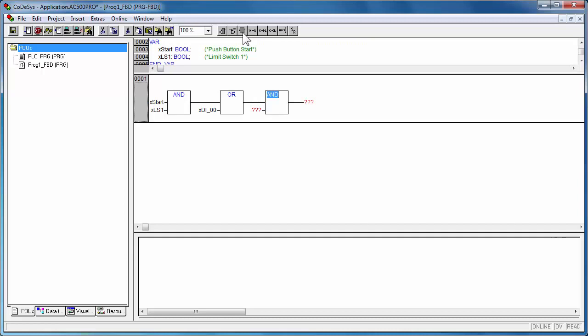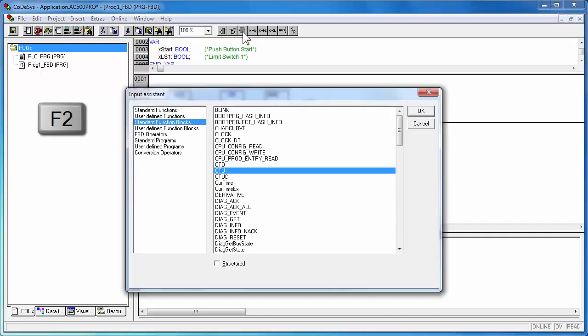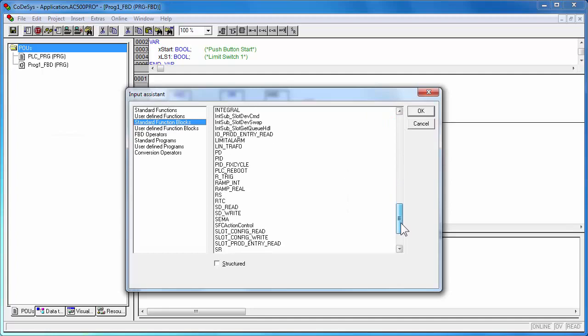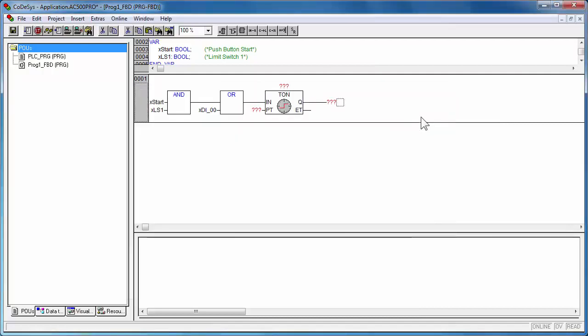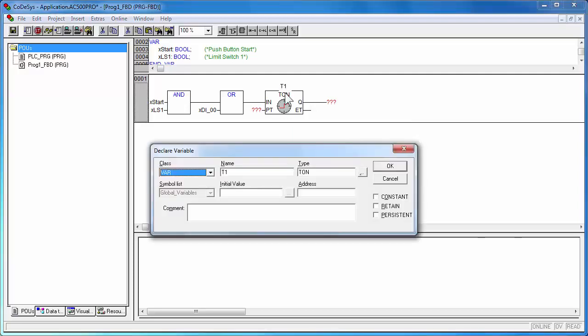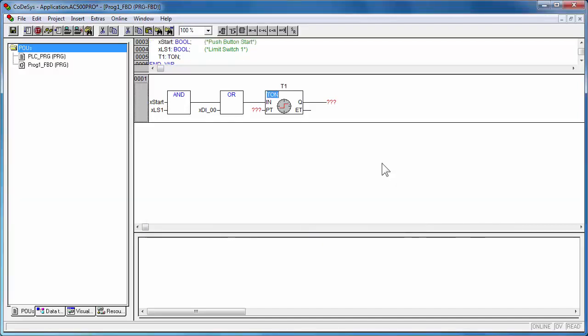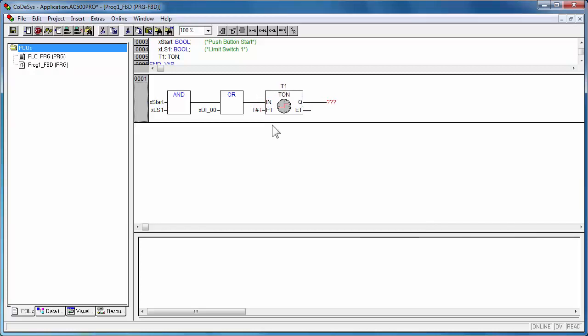Likewise a timer function block TON, could be programmed with appropriate input output parameters. The preset time of timer can be a constant time. The value must be in milliseconds, seconds, minutes, hours or combination of them.